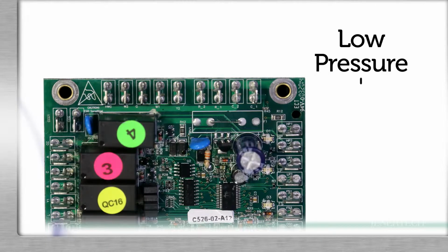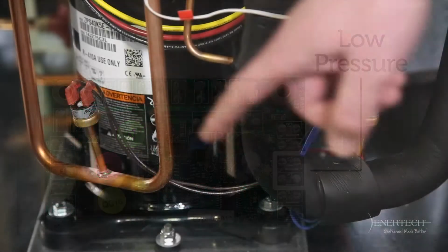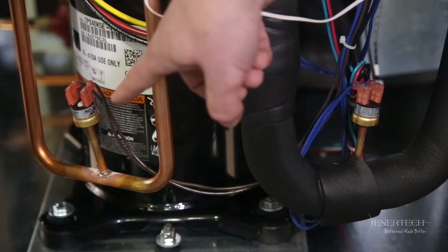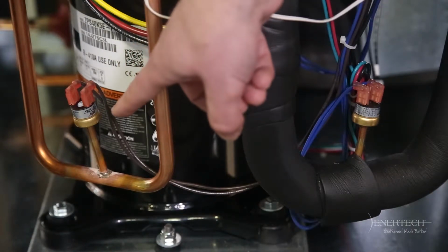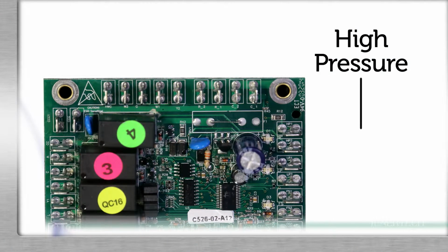Note, if the low pressure switch is open before startup, then the unit will not start upon receiving any Y1 call and will lock out instead. If the high pressure switch opens, the compressor operation will be interrupted and the control will go into fault retry mode. There is no delay between the time the switch opens and the board entering into fault retry mode. There is also no delay of switch monitoring at startup.